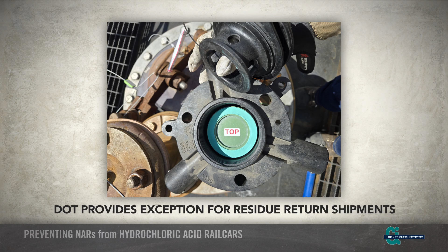Note that the removal of the rupture disc is not required on tank cars that contain residue per DOT regulations. Not removing the rupture disc and instead leaving it in place during inspection helps prevent errors in reassembly and therefore reduces the chances of an NAR. It is recommended that you refer to the DOT regulations in 49 CFR Part 173 and consult your supplier for more detailed requirements and instruction on inspecting rupture disc assemblies.